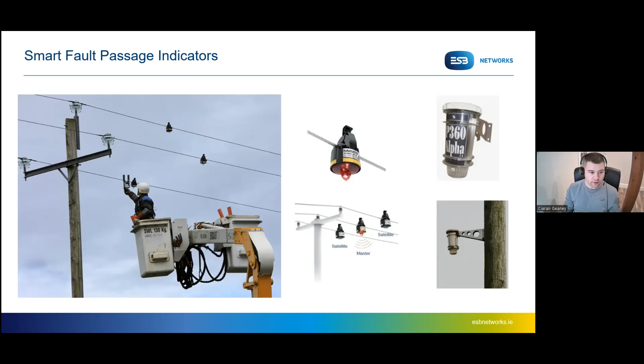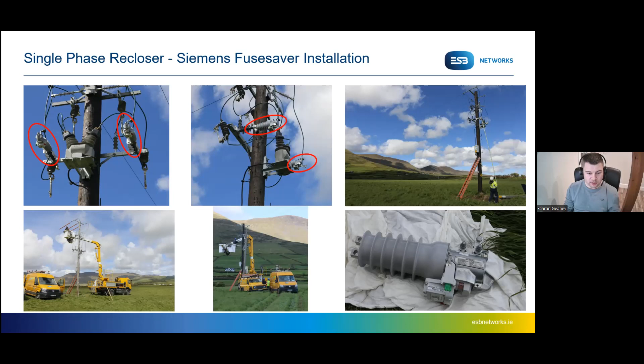Another technology that we deployed in Dingle was single phase reclosers. And the real benefit of these devices are on our single phase networks where we have non-permanent faults. So things like two conductors clashing together, a branch hitting the conductors, a bird strike, any of these sorts of non-permanent faults where typically the fuses would blow and our customers could be out for anything up to a couple of hours. Where we have these single phase reclosers, the devices will trip when they see the fault, and then after a small amount of time, around a second or so, they'll reclose, and if the fault is gone, those customers will be re-energized and be on supply. However, if the fault is permanent, like a line on the ground or something like that, the devices will trip open and stay open until the repair crews arrive and fix it.